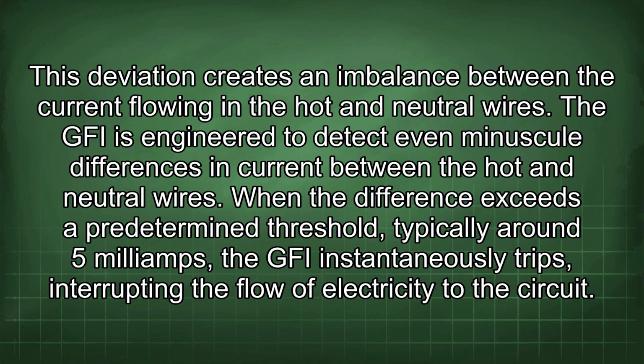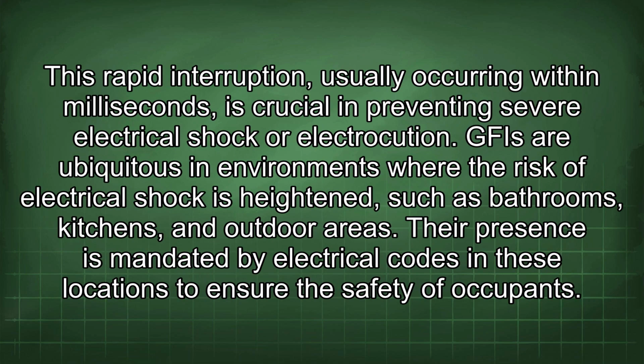The GFI is engineered to detect even minuscule differences in current between the hot and neutral wires. When the difference exceeds a predetermined threshold, typically around 5 mA, the GFI instantaneously trips, interrupting the flow of electricity to the circuit. This rapid interruption, usually occurring within milliseconds, is crucial in preventing severe electrical shock or electrocution. GFIs are ubiquitous in environments where the risk of electrical shock is heightened, such as bathrooms, kitchens, and outdoor areas. Their presence is mandated by electrical codes in these locations to ensure the safety of occupants.